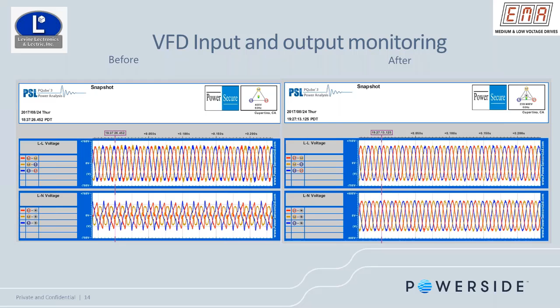And this also is a good indication or example of voltage sag that results in significant current draw, and then eventually the VFD tripped, right? And it caused instability on our DC power supplies, because when we lose power or the power dips, the way drives work is that when a diode is turning on, the capacitor, we have capacitors in our low voltage power supplies, we have them in our power cells and so forth. So the job of the capacitor, when the diode is switching on, is to store charge. As the diode turns off, the stored charge on the capacitor will then provide power, and this process keeps repeating.